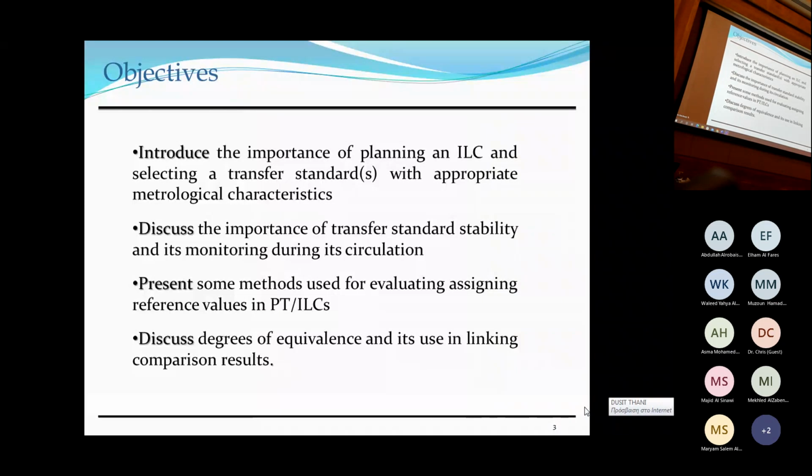Example, in comparison, it's related to gauge block as a reference. In PT, there is no... No. It has nothing to do with the level of accuracy necessary. Because in the secondary labs, they don't have gauge block interferometers. So you have a micrometer which moves around, and they calibrate that. So it doesn't matter. The difference is that PT is conformity assessment through ILC.